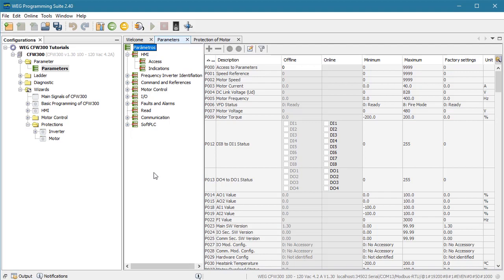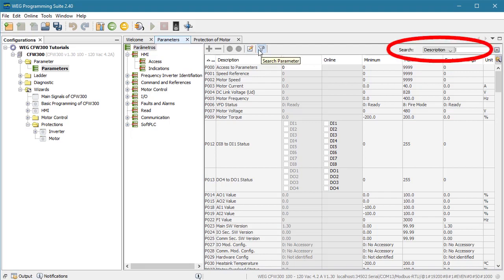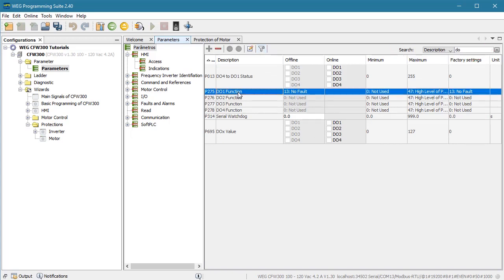This is the free WEG programming software, or WPS. It isn't connected to my drive right now — I'm just going to use it as a quick parameter lookup tool. If we select all parameters and then search on DO for digital output, we see that Digital Relay Output 1 defaults to no fault.